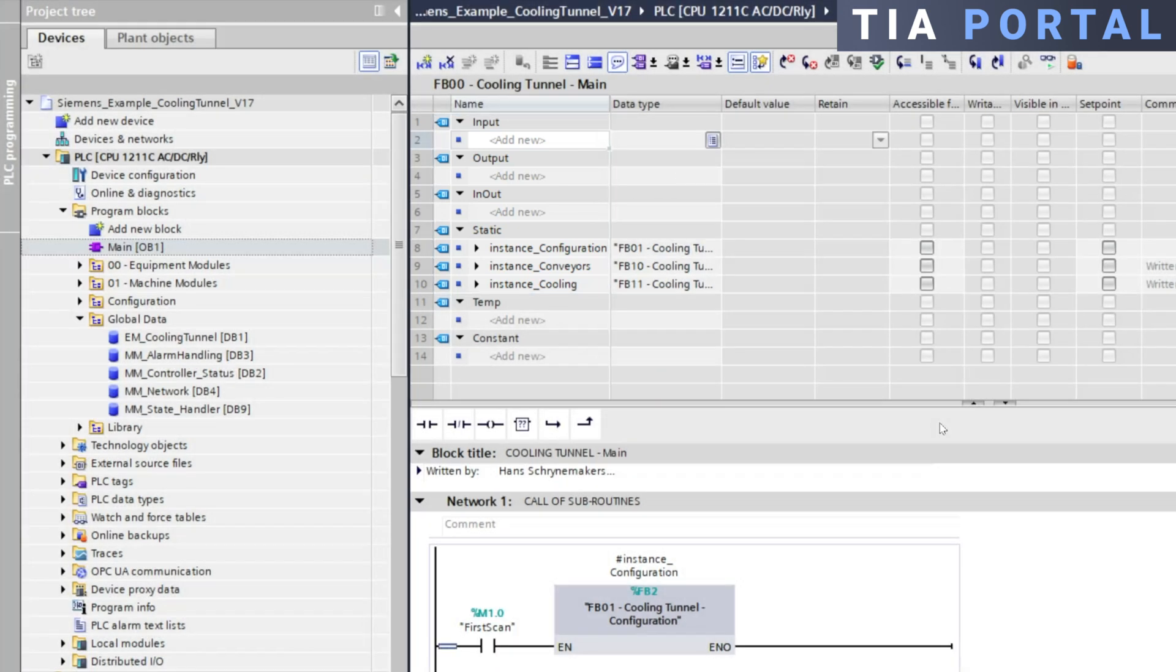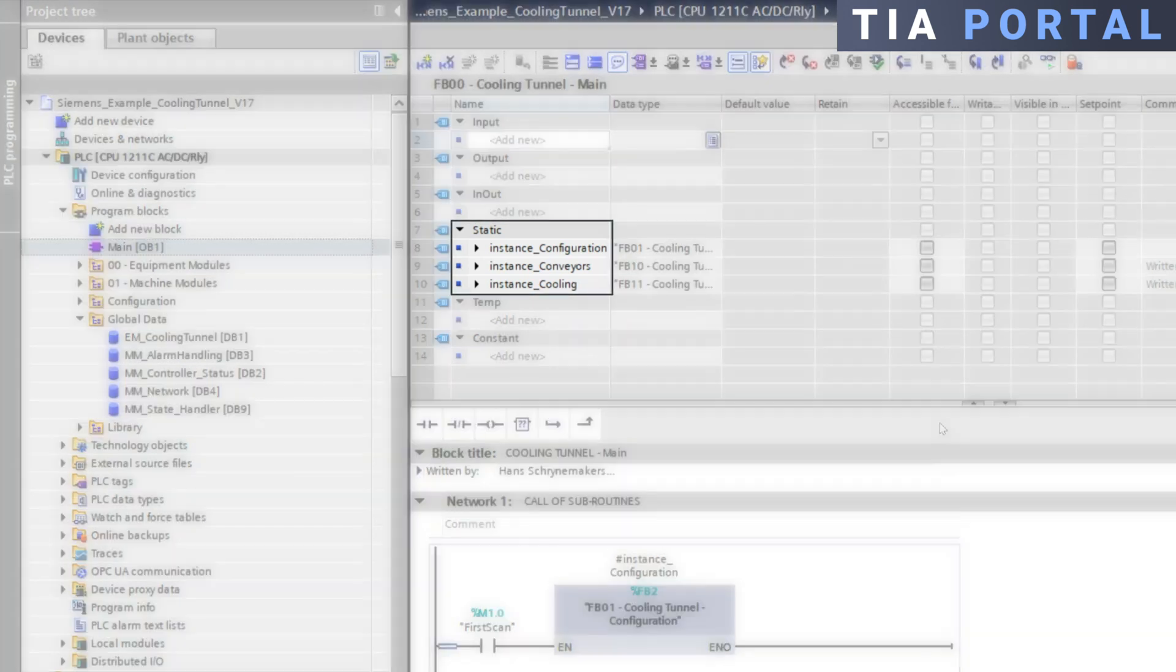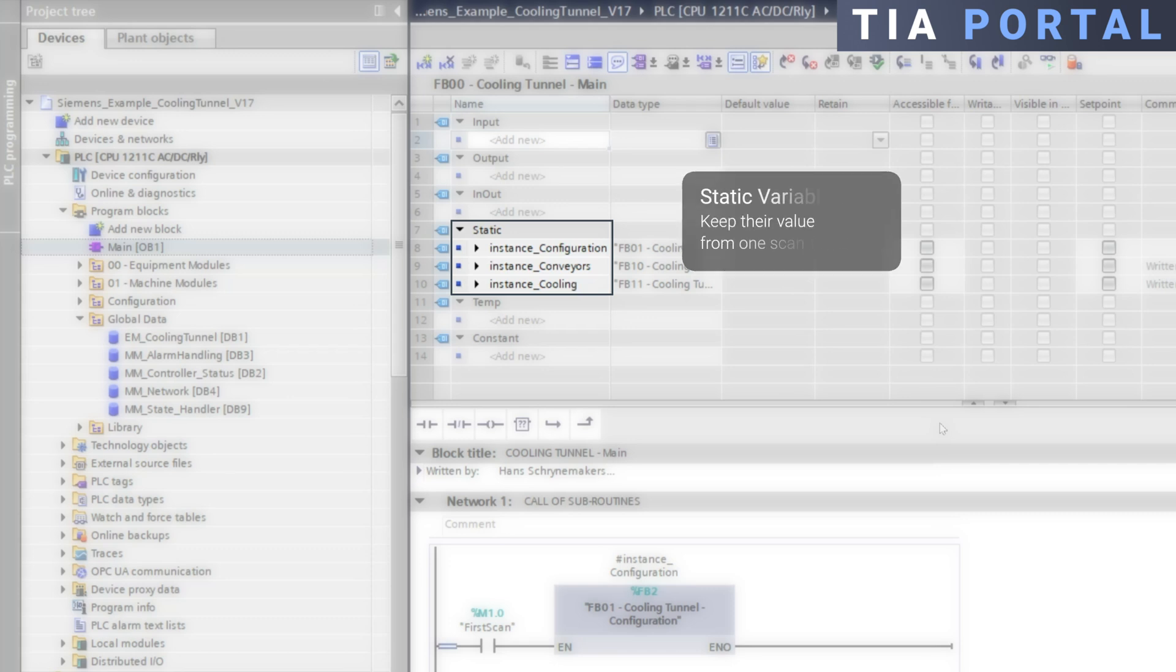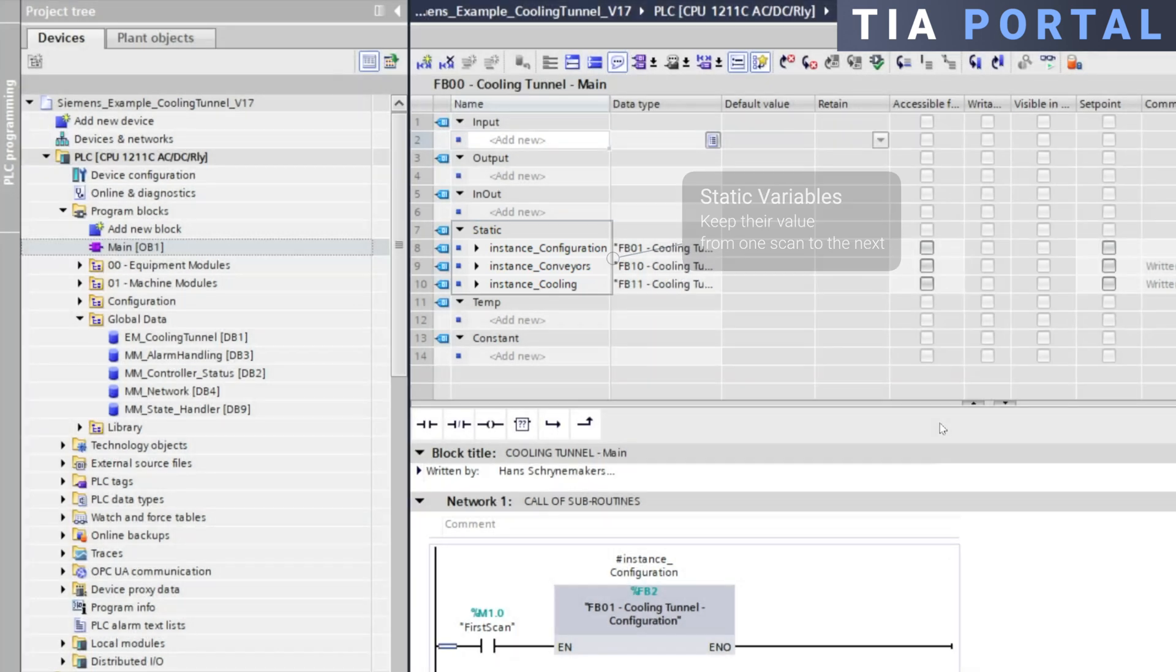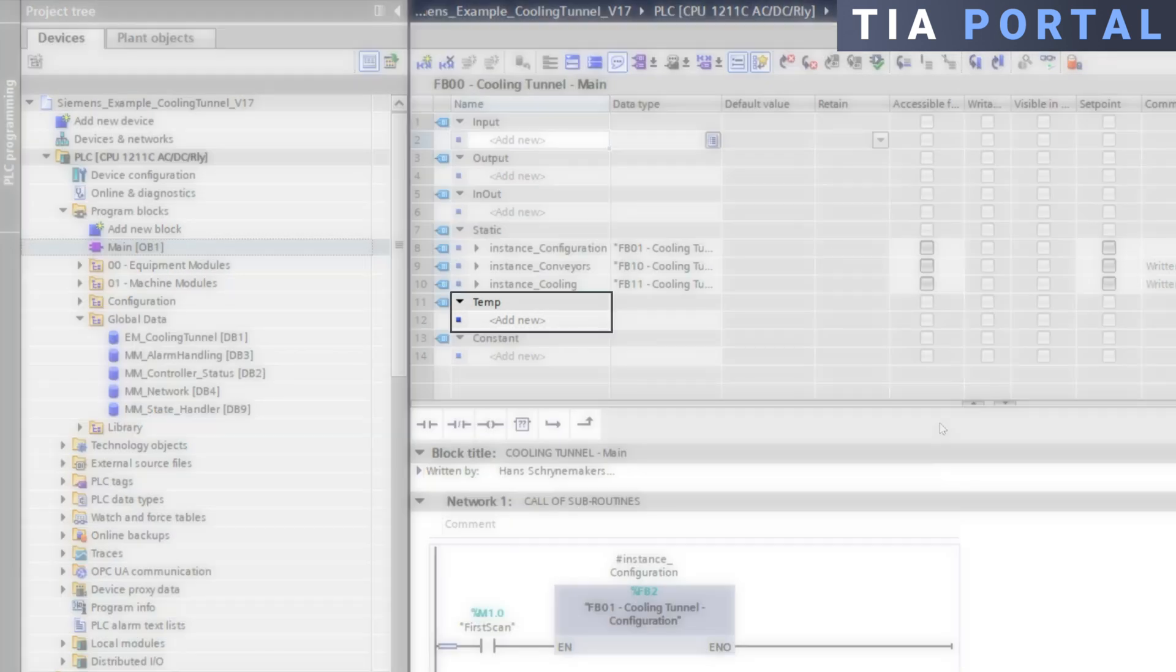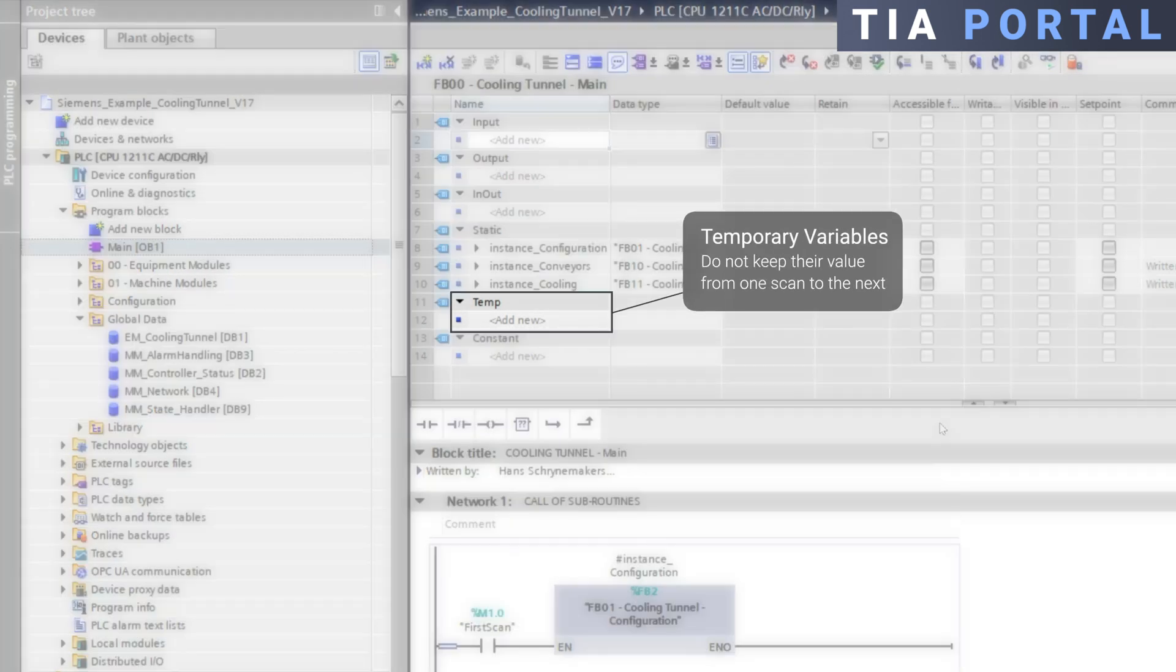Furthermore all variables defined in the static memory area are persistent across program scans retaining their value from one scan to the next. On the other hand variables created in the temporary memory area exist only during the block's execution and they are discarded once the execution is complete.